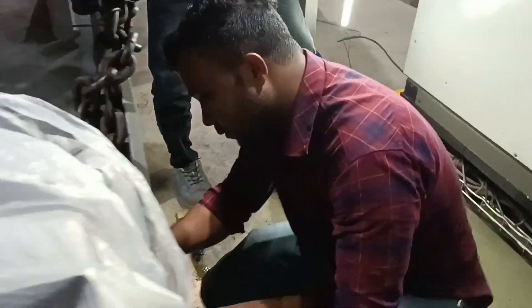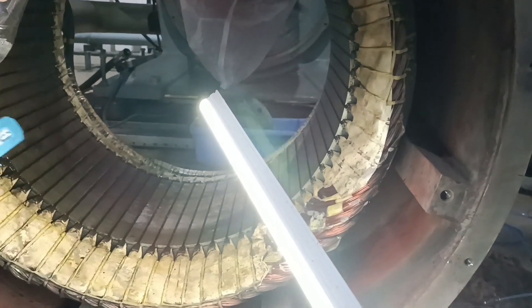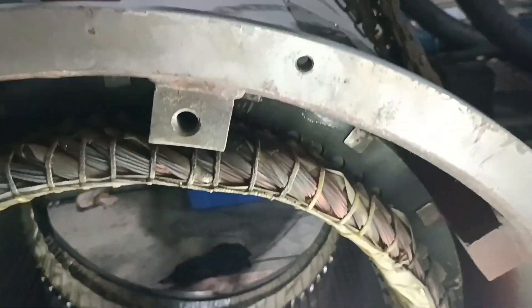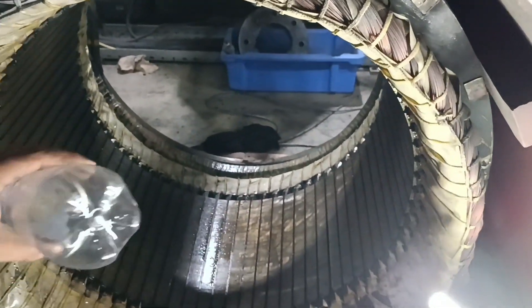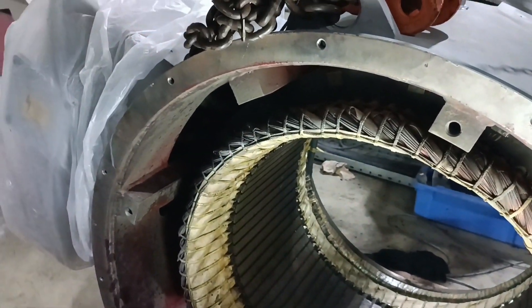If the motor is an air-cooled system, a lot of dust is carried inside through the coil and accumulated there. That's why the motor coil gets shorted with the body or coil-to-coil — that's why a big problem happens. We contacted the OEM of this motor and they suggested at least 70 lakh BDT for the price of replacing this motor.